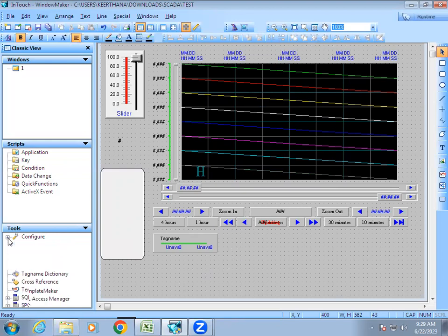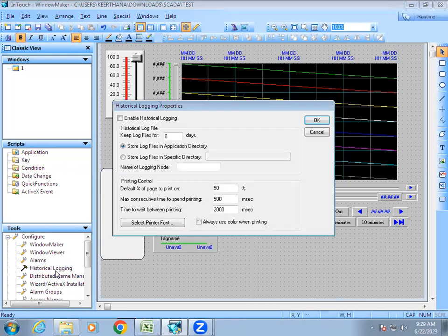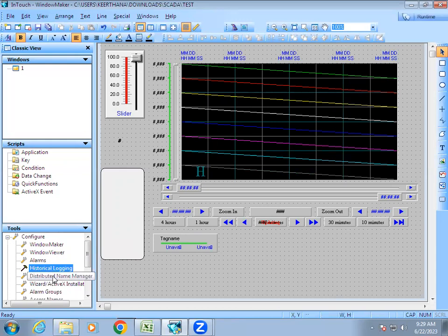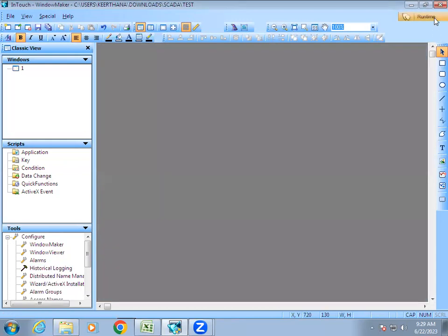There is one more step: in Configure we have 'Historical Logging.' Right now the SCADA software records past data but won't display it in the chart until we enable this option. Go to Configure, then Historical Logging, put a tick mark on 'Enable Historical Logging,' and give OK. After that, go to runtime.